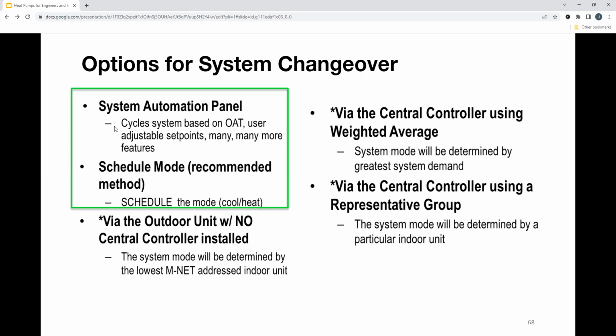I also like the fact that, going back to an office application with a condenser and 4 fan coil units, if you're looking for a way to change it over, I do think having a central controller and dedicating a local controller to be the master controller or the representative group works well. Let's say there's a CEO office and there are three other offices. That CEO, basically the boss, is going to choose that mode and change over the system accordingly. So make sure when you are using commercial heat pumps that you do use some form of changing over the system. Just don't leave it how it is, because you will run into complaints and occupants are going to wonder why they're not receiving cooling or heating mode depending on the season.